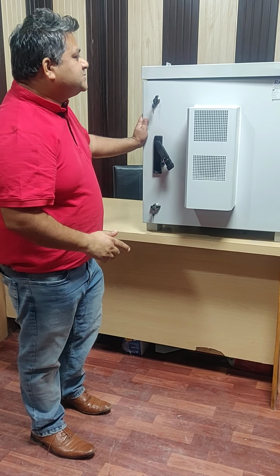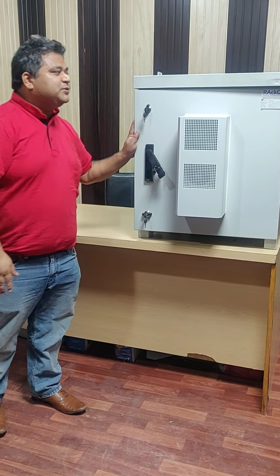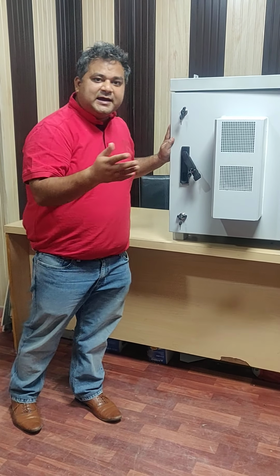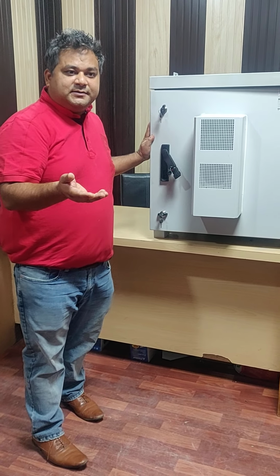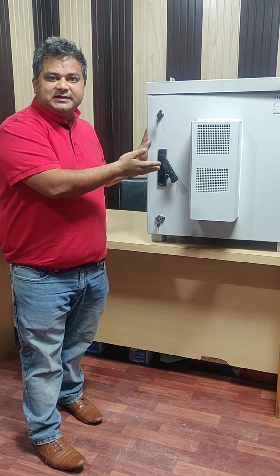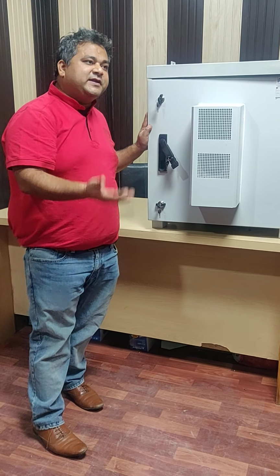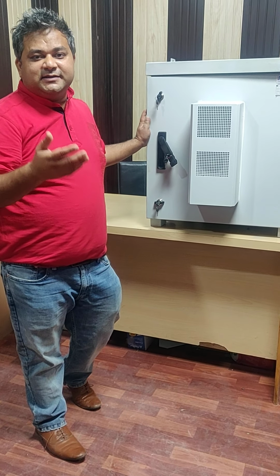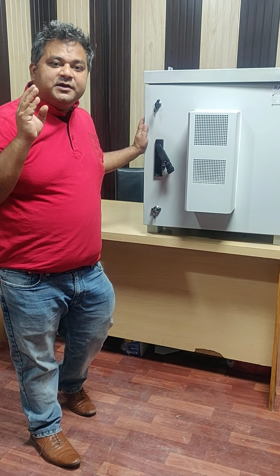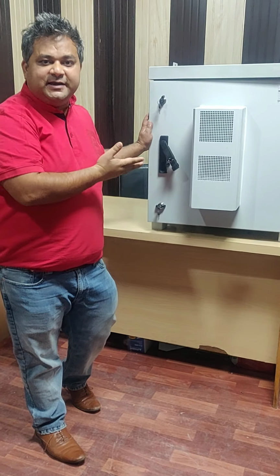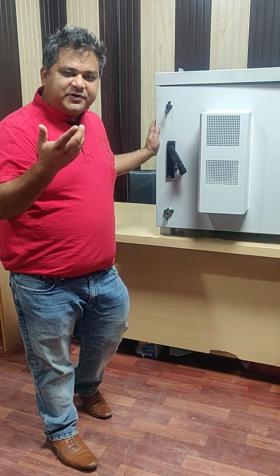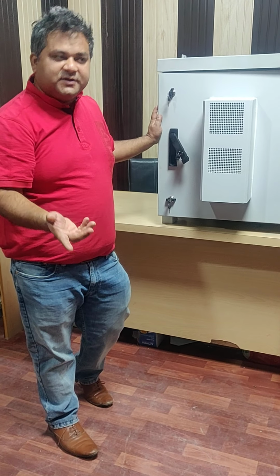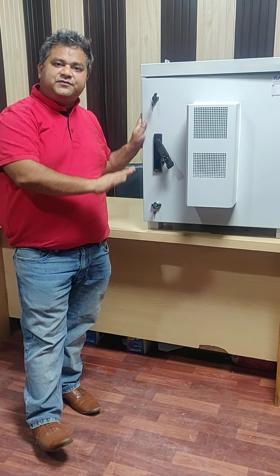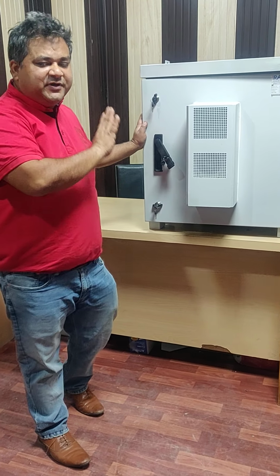So this was a simple demonstration. This is the smallest and lowest capacity we have available, the 300 watt, and it is very useful when you have 1, 2, or 3 switches inside along with one small 500 VA, 600 VA, or 1 kVA UPS. That can maintain 24, 25, 26 degrees Celsius very easily.